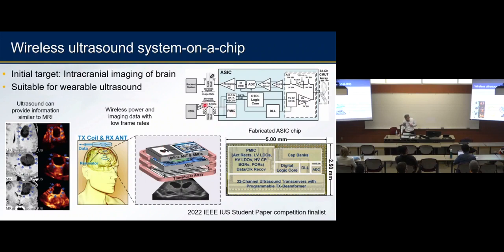And for that, we're using around 40 megahertz transmission through the skull. And then this chip does basically everything about imaging: transmit beamforming, receive beamforming, and then sends the data out. And the nice thing about this method is that the imaging doesn't need to be fast, because the brain is not moving a lot. So you can have one frame per second kind of rate, meaning that I don't need to be fast and power hungry. So we can just do it slow enough. And actually, we get some images out of this system, which will be presented in the upcoming symposium in October.